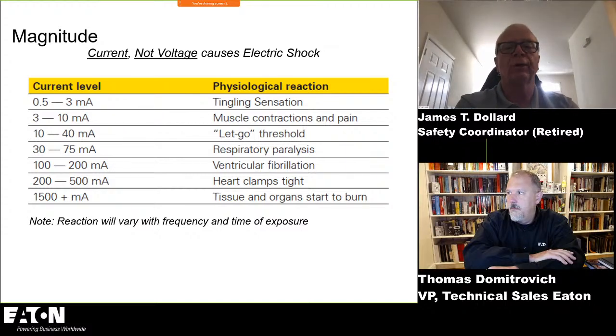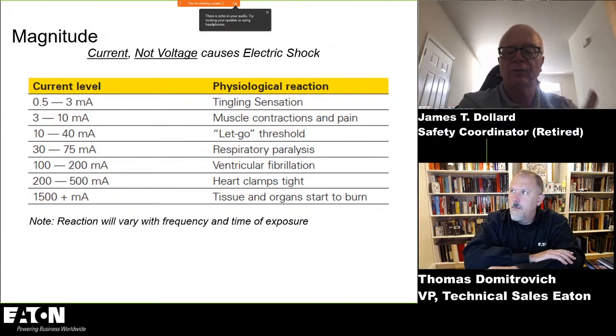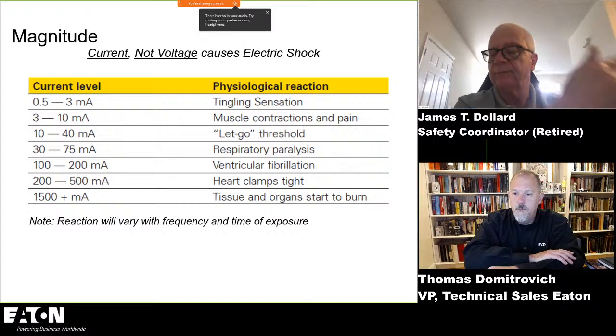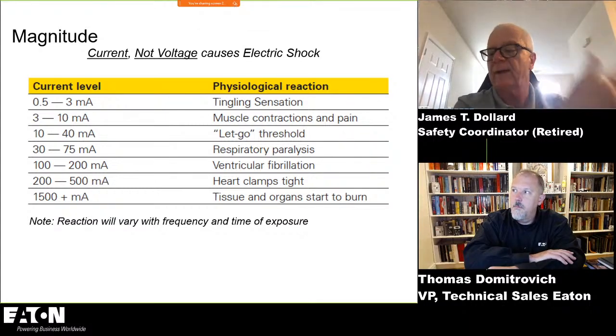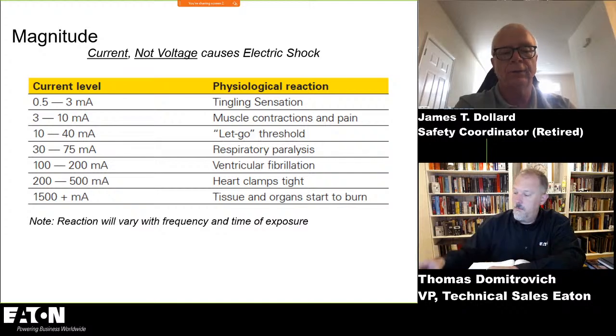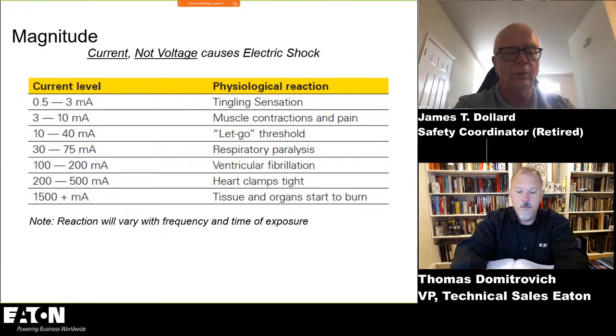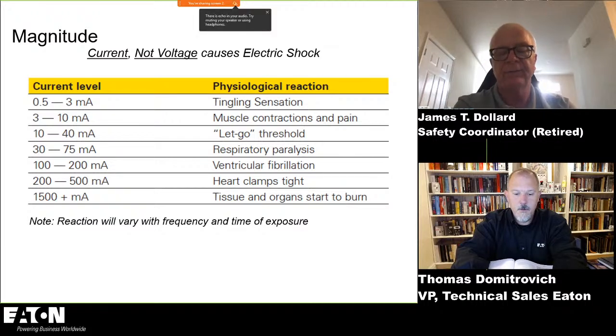Well, one of the reasons is that OSHA, in 1926.21, and there's a requirement in the general industry standard, says everybody has to be taught about the hazards in their workplace and the potential of damage or injury to health. So they have to understand all of those things. But when you point out to the electrical worker that they can get to the let-go threshold at 0.01 amp, they understand that's not a lot of current, and that if that flows through their body, all of their muscles are going to tense up and they're not going to be able to let go. So it's extremely important for them to understand this.